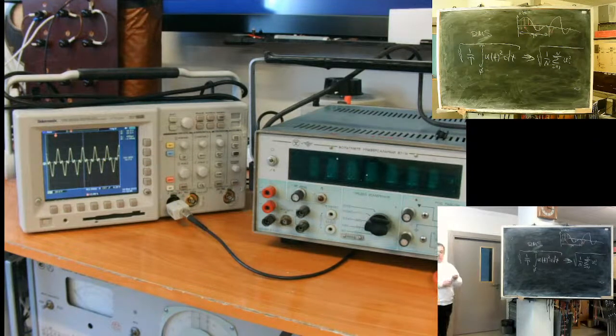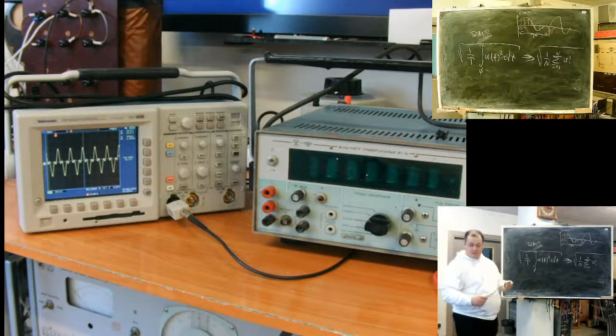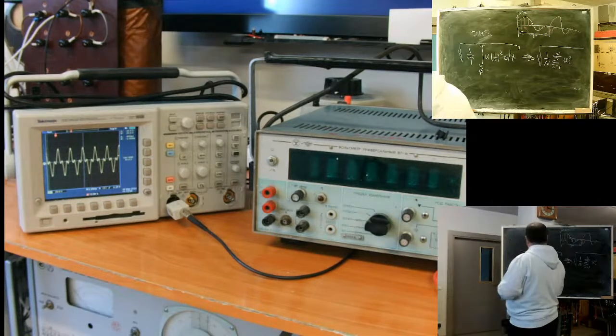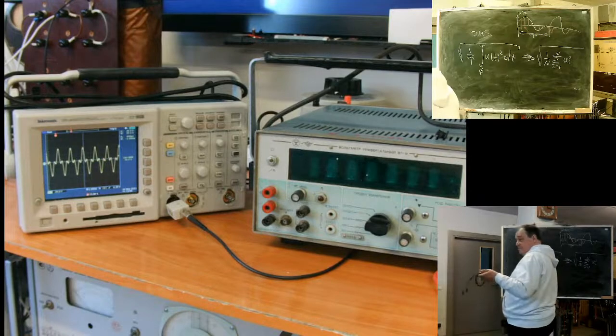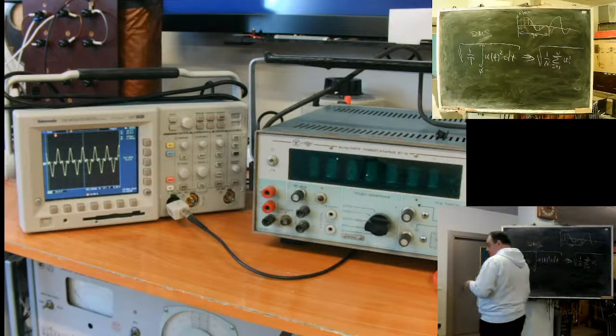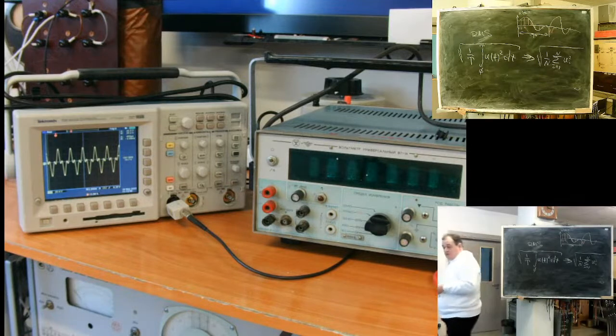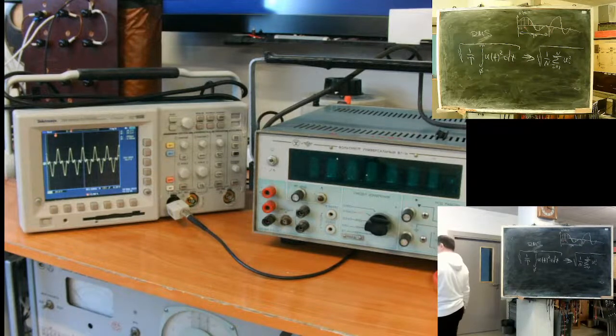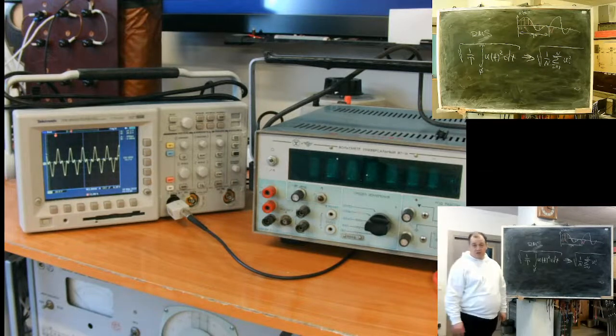What can we conclude? Moving coil instruments will have an error of some 10%. Moving iron, okay, but limited in frequency, and puts a high load on the measured circuit. Dynamometers, okay, but we need to account for the inductance they introduce into the network.